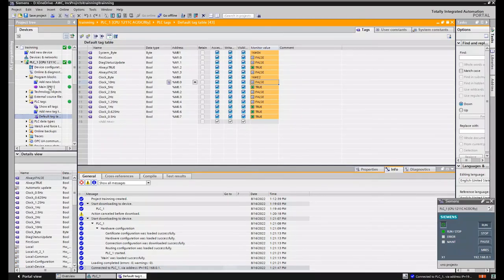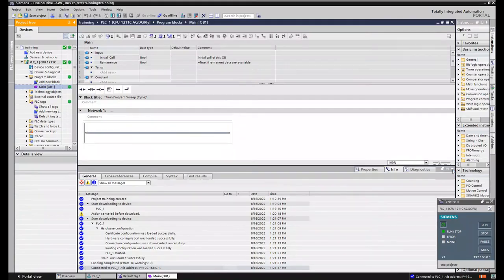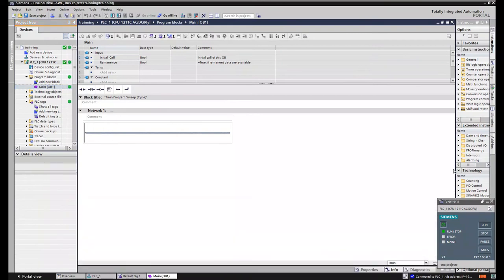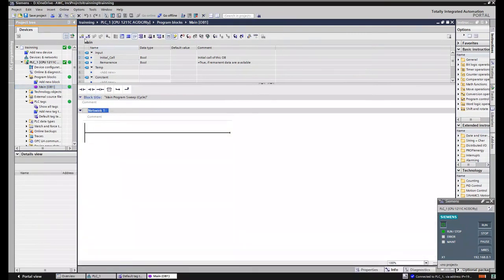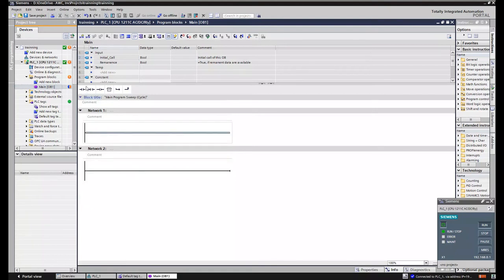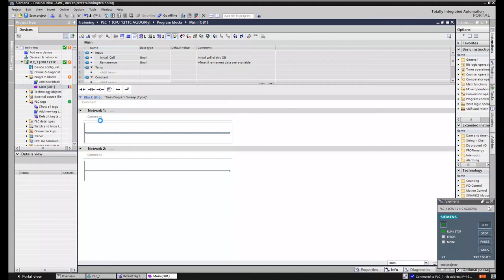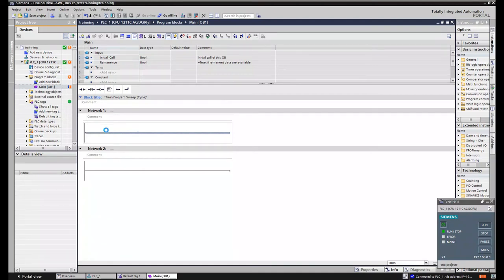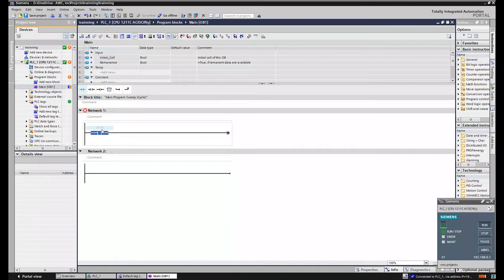So we're going to open up OB1 on this menu. And I'm going to add a second network because I'm going to first do an always true. And I'm going to have a blink that happens on. So like let's just say you had a proximity switch that was broken, but the machine doesn't technically need it, and you just need it to run until we get the new part in. We could add that always true to keep the prox on so that something can still run. So let's just add that to our project. Just going to add this, always true.